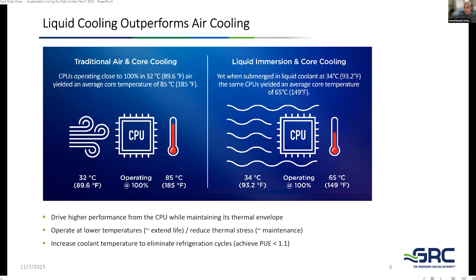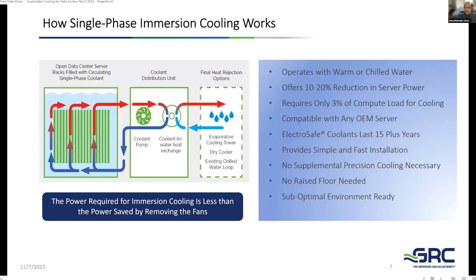And that is the secret behind liquid immersion cooling, where I talked about a PUE of 1.1. Because effectively speaking, depending on the density of the racks, we can provide a solution where you don't need a refrigerant cycle at all. It is simple dry coolers, just some pumps and fans which are operating and helping get rid of the heat. How does it work? Conceptually, it's a very simple idea. We take a tank, which is nothing but a horizontal rack. We fill it up with the coolant and we insert the servers inside that.